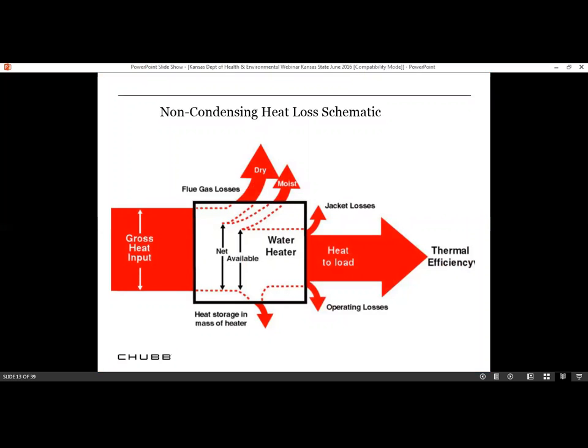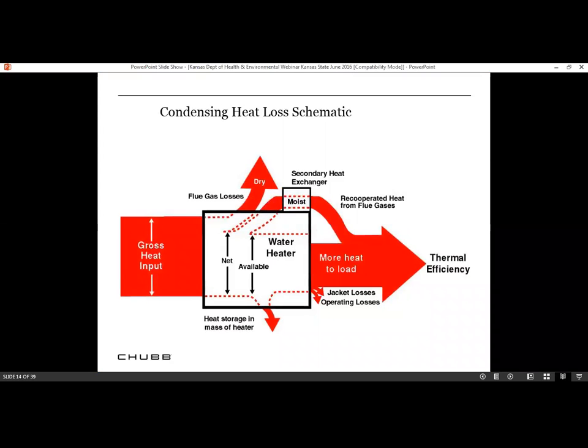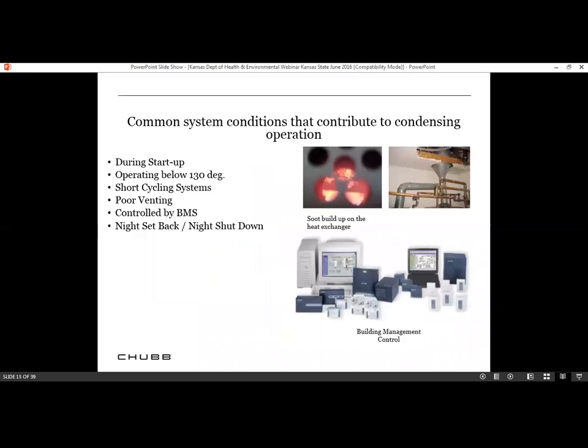Non-condensing boilers, I'll just briefly go over this slide and the next one. But non-condensing boilers, if you look at the very top, you have the flue gas losses to dry and moist, and jacket losses. And then the heat input goes to the load, and that's where you get your thermal efficiency. Now, condensing boilers, on the other hand, the moist air actually goes to the load, your jacket losses are reduced, and your thermal efficiency is increased. And the way they do that is that there are two stages of condensing.